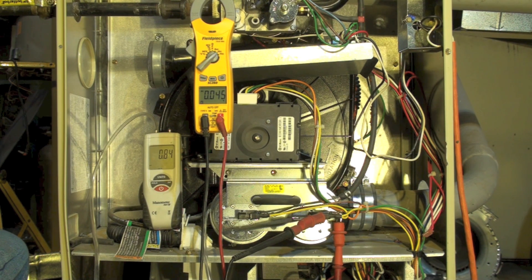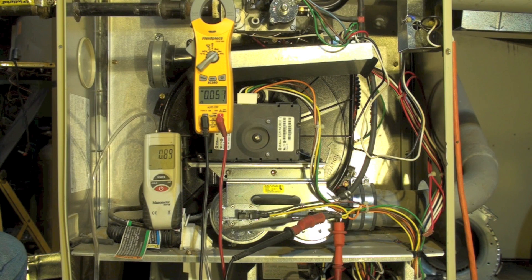And you can see our vacuum is dropping because the RPM of the inducer is going down. You see it drop down to 80, and I think it made it at like 77 or 75, so it's going to go down almost to that and just right back up a little bit. And then it's just going to sit right in there. That gives the highest efficiency for the burn because we're not bringing in too much cold air into the burn and getting too much excess air. We're reducing the amount of excess air when we reduce the speed of that inducer, and so you get a little bit more efficiency out of the burn.